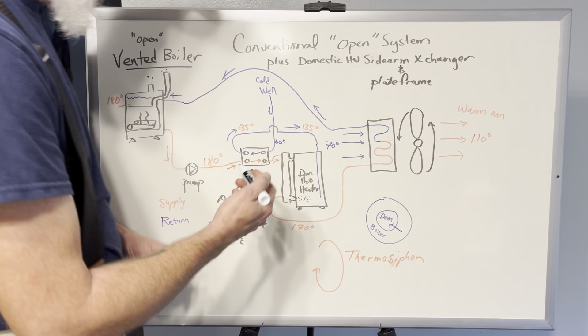would be, well, I guess I could say a minimum would be a 10 plate. That's probably going to be small for most of your families if you have a lot of people. I would probably recommend a 20 plate is going to cover a lot of bases. You got to be careful because these plate frame heat exchangers can have such high output, you can outrun your boiler and get really cold water going back, and that's not good. So your size depends on what your needs are. But basically what happens, let's look at the boiler water side first. We talked about the counterflow.